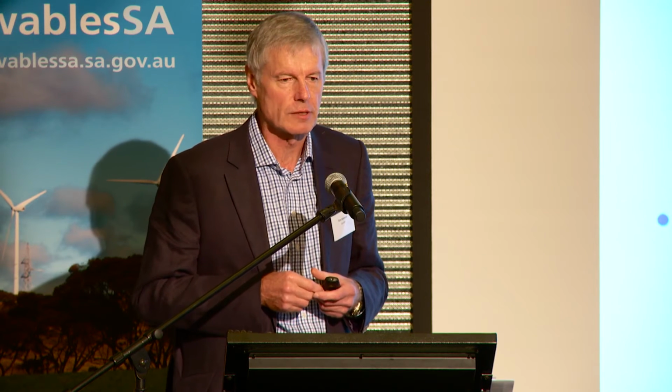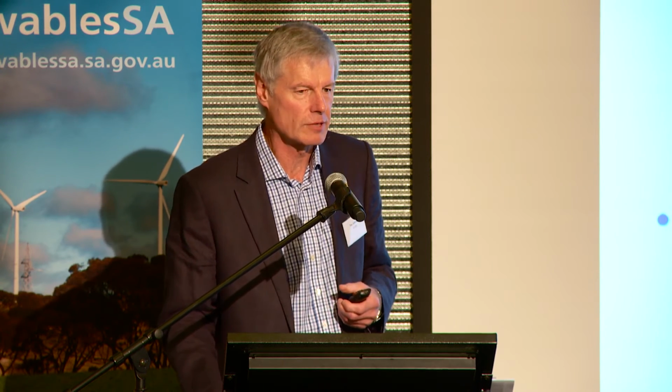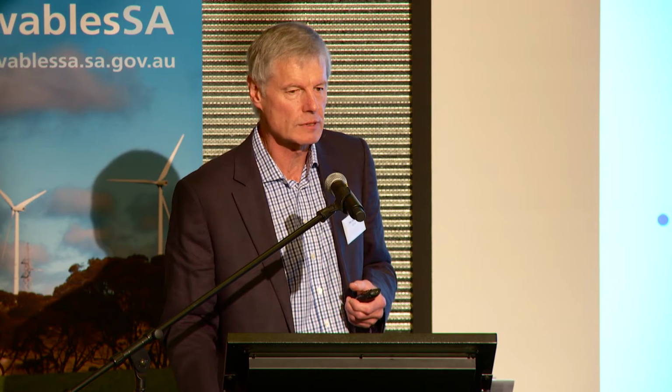You burn the wood chips or you gasify the wood chips, and I've been involved in both of those processes. Typically you burn the wood chips, the combustion gases go through a boiler, you make some high pressure steam, you use some of that steam for the production of the pellets, and you use some of the steam through a steam turbine to make electricity.